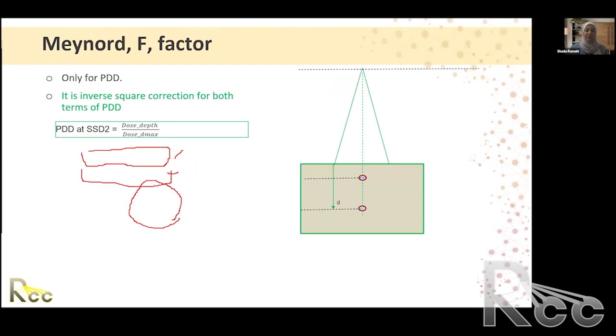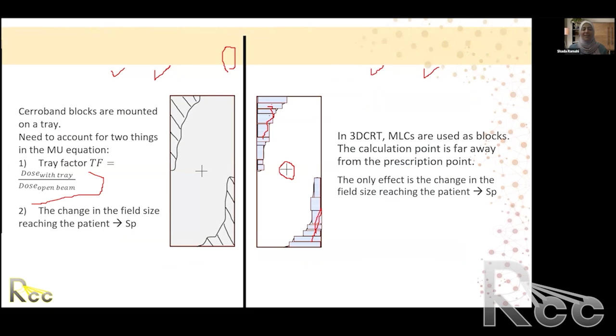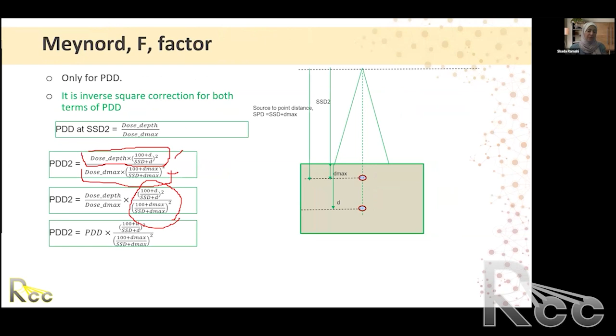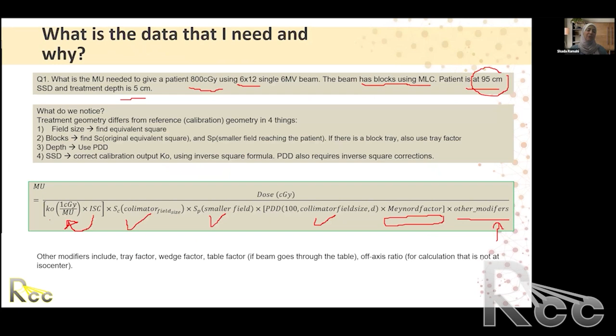If the prescription point is not the isocenter, so far we have assumed in our example, let me go back quickly. Almost there, yeah. So far, we're assuming that we're prescribing to the isocenter, so there is no off-axis issue. There's not a problem here. But if your prescription point is not at the isocenter, which could happen if we're doing tangential breasts or chest wall, it could also happen if I'm doing lung or maybe pelvis, etc. Then I need to have an off-axis ratio. So everything comes here in the lower part in the denominator, because everything is trying to correct back to the geometry where this is true.